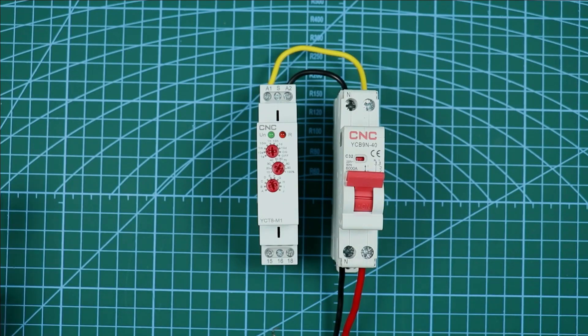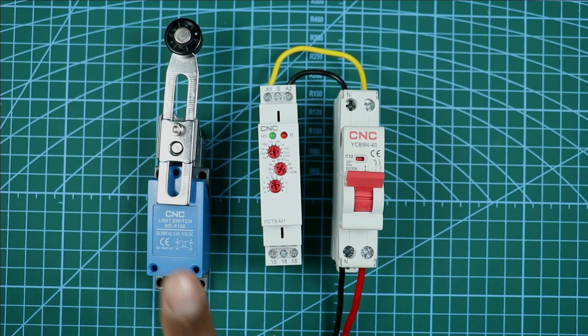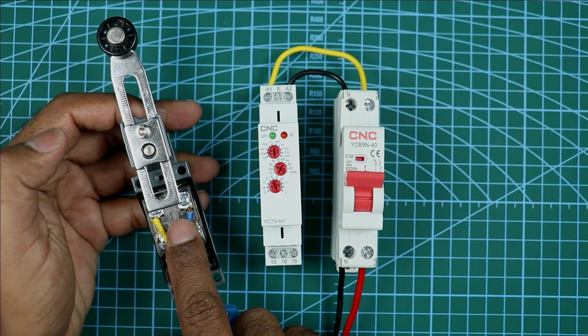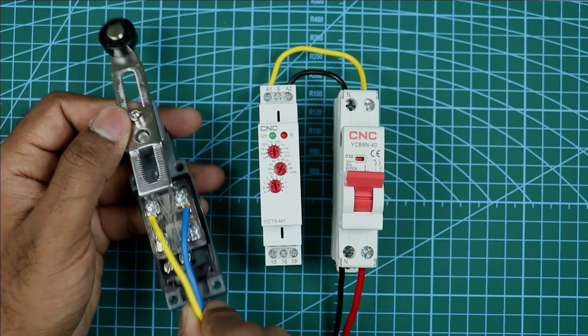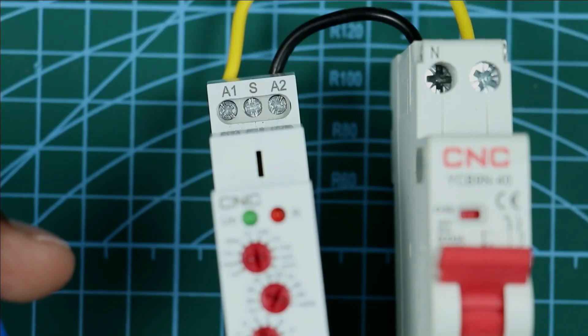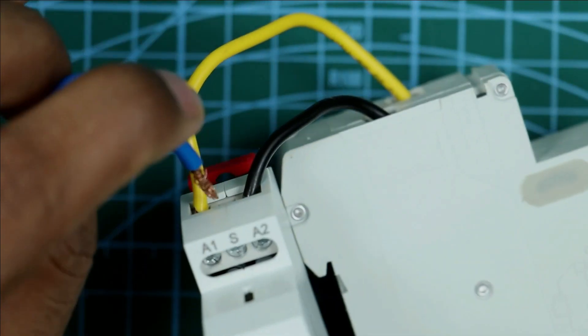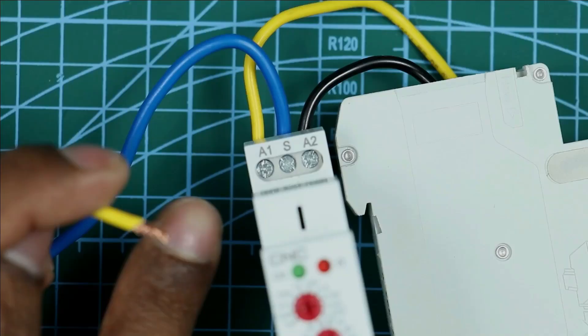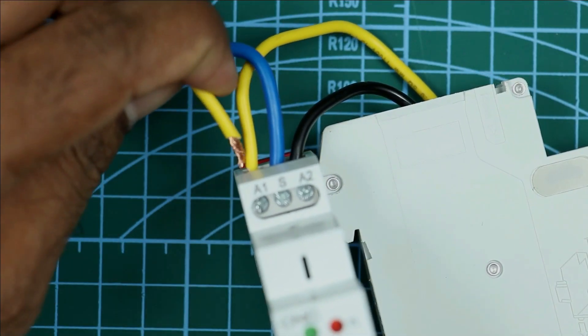Now this timer needs to be operated through limit switch. For this, at the NO contact of this limit switch, connect two wires. I already connected two wires. Connect one of the wire with timer. You can see S terminal on timer. At this S terminal you have to generate signal. So connect this end of wire with this S terminal. Take another wire of limit switch and connect with A1 terminal of the timer.